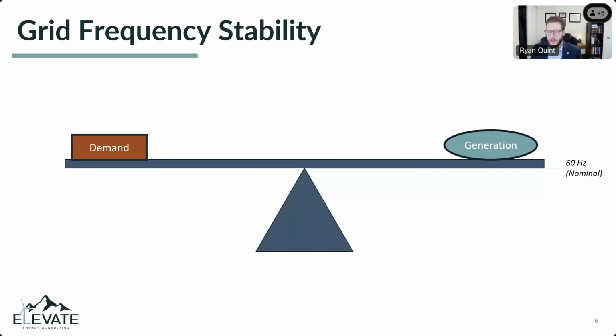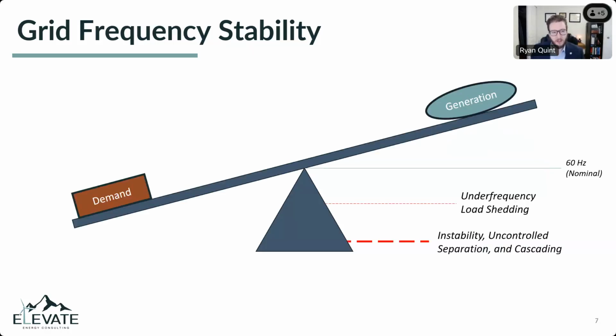But we don't plan the system for the loss of that generation in addition to an unknown amount of generation resources unexpectedly tripping off. So as demand starts to exceed generation, the scale starts to tip, and we have thresholds out there on the system where we have under frequency load shedding.